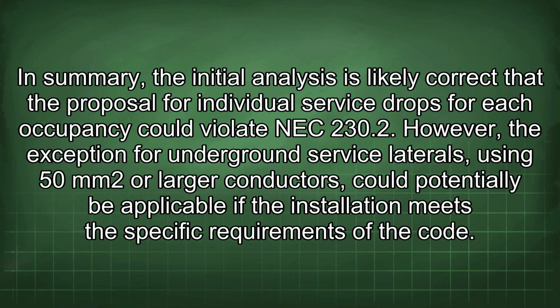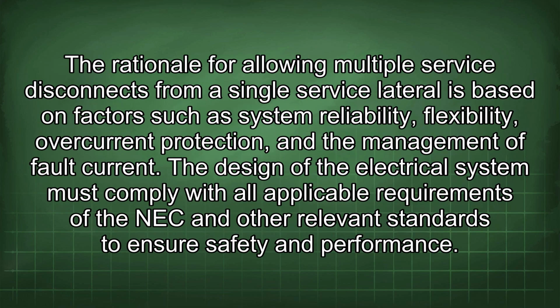In summary, the initial analysis is likely correct that the proposal for individual service drops for each occupancy could violate NEC 230.2. However, the exception for underground service laterals using 50 mm2 or larger conductors could potentially be applicable if the installation meets the specific requirements of the code. The rationale for allowing multiple service disconnects from a single service lateral is based on factors such as system reliability, flexibility, overcurrent protection, and the management of fault current.